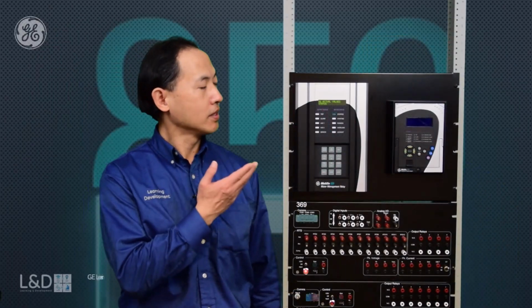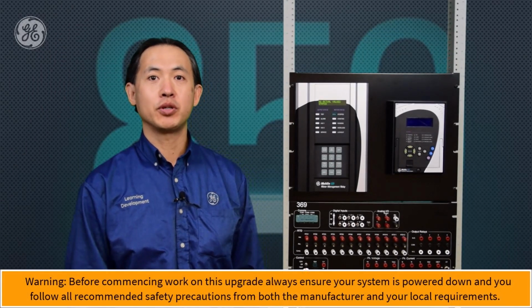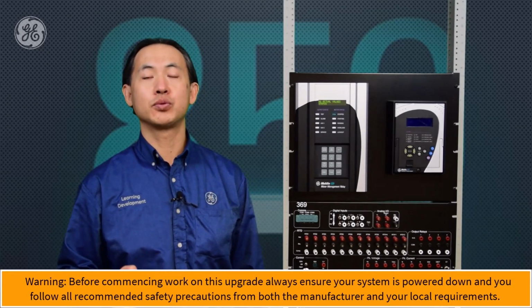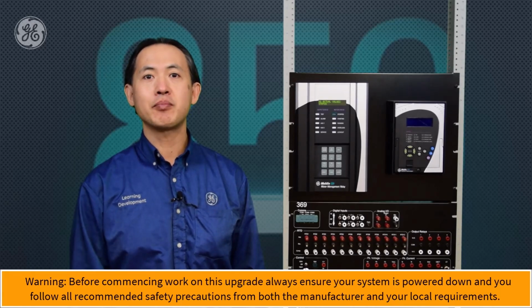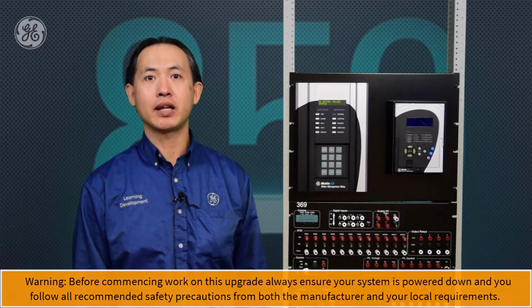Now we have one 369 relay on the mounting rack. We're going to replace this with one 859 relay. There will be 3 steps. The first one is to do the setting file conversion from 369 into 859. This can be done automatically in the 8 Series EnerVista software.